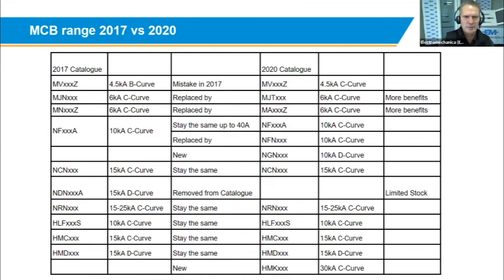The difference between MJN and MJT was that the MJN could not take accessories. It could not have an add-on earth leakage device, where that was possible with the MJT. The MN that we replaced with the MA, again, it has more benefits. The MN also could not accept accessories, where the new MA can. And there's just a summary of changes within the catalog.